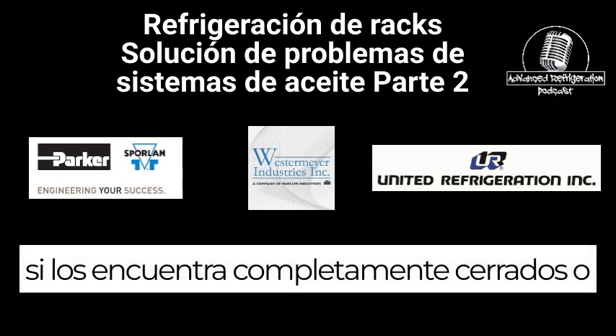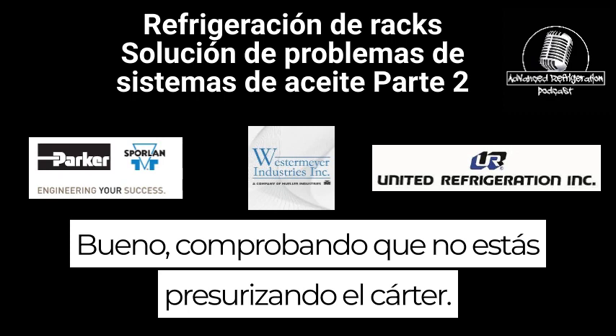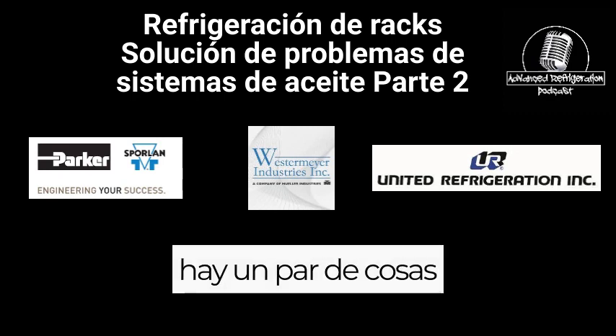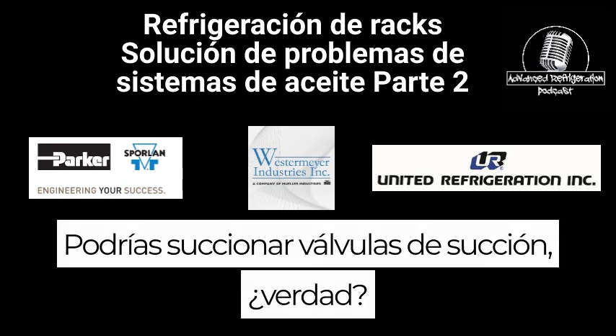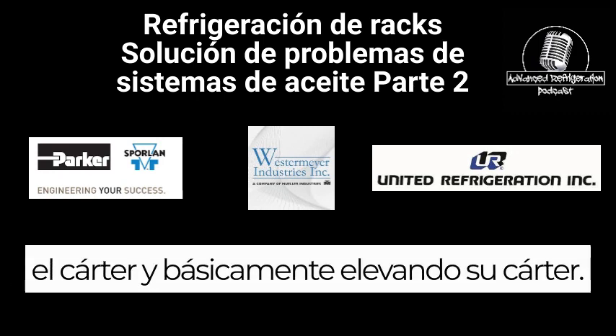If you find them all the way closed or open, generally, so three helpful hints is checking to make sure you're not pressurizing your crankcase. There's a couple of things that could cause this, right? You could have bad suction valves, right? You could have discharge flowing back into the crankcase and basically elevating your crankcase.